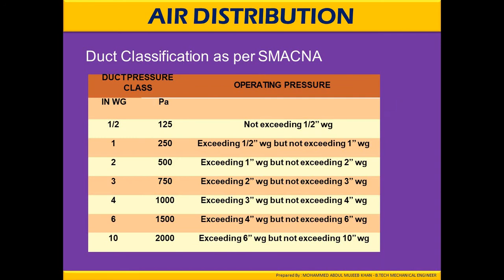Duct classification as per SMACNA is given in inches of water gauge and in Pascals, with operating pressures defined accordingly. For example, if the static pressure is 125 Pascals — which is half inch of water gauge — the operating pressure should not exceed half an inch of water gauge.